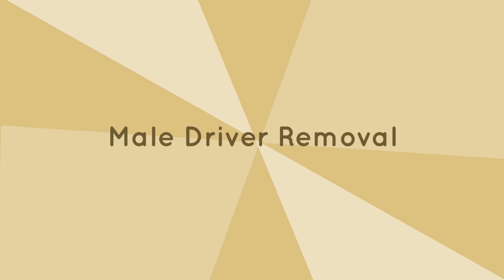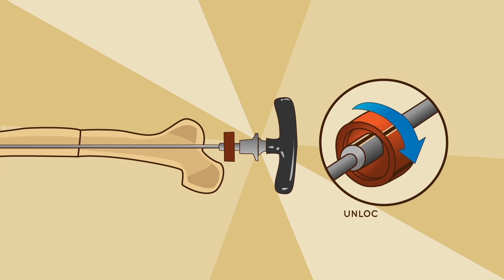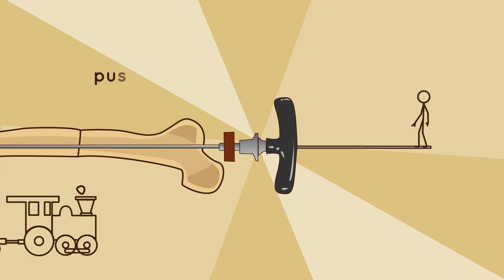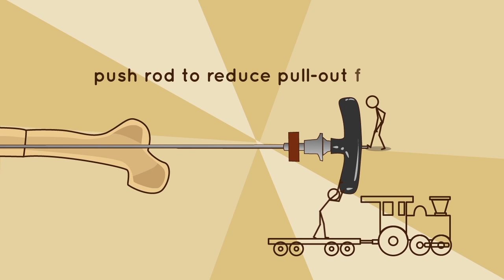Male driver removal. Unlock the male by rotating the eccentric ring to the unlocked position before removing the male driver. Removal of the male driver is done with the assistance of the pushrod PSR-100 to reduce pull-out forces on the nail fixation while the driver is pulled back.